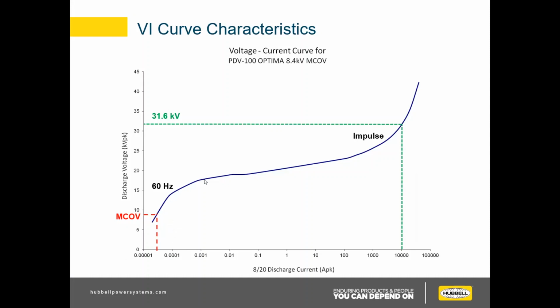And the higher you go up this curve, the more current it conducts, of course, and the more heat it generates. So your TOV region will be somewhere right in here, and you're in the knee of the curve here. And so you're conducting a tenth of an amp, or a hundredth of an amp, enough to generate heat. And heat is never good. So TOV is a very, very common failure mode for arrestors. TOV generates heat, and the arrestor eventually gets into thermal runaway. The hotter it gets, the more current it conducts, until it eventually just can't cool itself off anymore, and then it runs away.